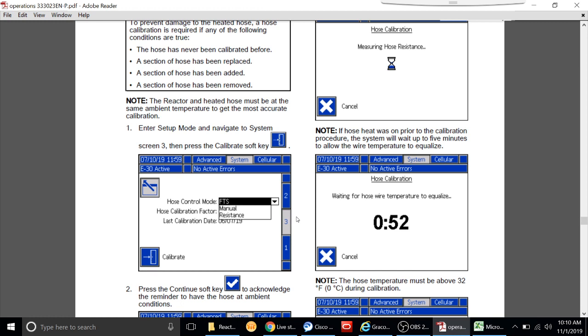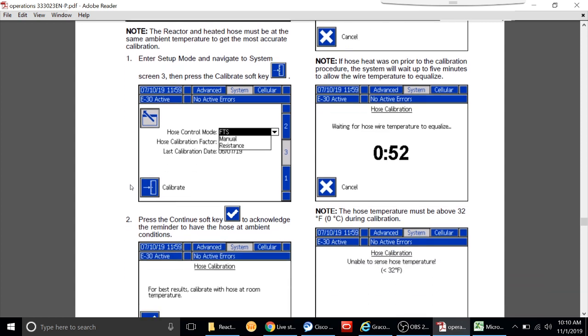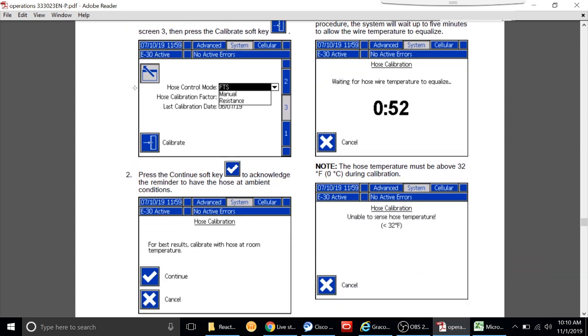In the past, we didn't have this, right? It was either FTS or you went to another spot to go into manual mode. But now what we're able to do is we enter into the window. On the top left part there, you see the window. You'll hit that soft key off to the left-hand side of it, and that opens up the window to what you see now where the FTS is highlighted. And then you'll hit enter. It brings the drop-down menu down, and then you select resistance.